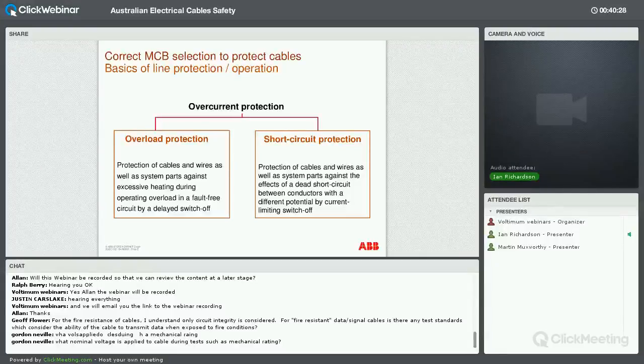And also we have short circuit protection, where we get into those areas of a much higher fault level, which we're trying, usually through the protection, to isolate very, very quickly, and that prevents a degree of energy going through to both the load and the cables and the general infrastructure of the building or the network that we're involved with.